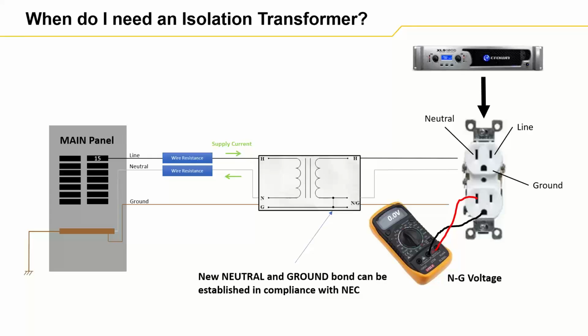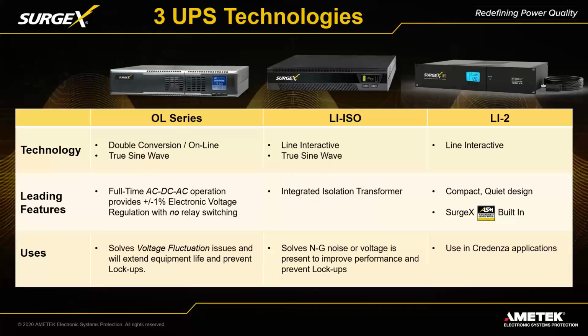But don't make the mistake of thinking that you can just add a neutral to ground bond at the outlet without using an isolation transformer. This is a safety shock hazard, and it violates both the National Electric Code and UL standards. They want a separate path for that ground to travel down. We can get into that in other webinars. But do not connect that neutral to ground at the point of use, unless, of course, the isolation transformer provides that for you.